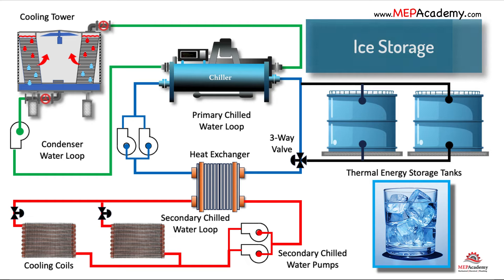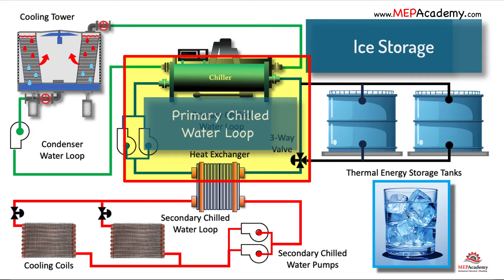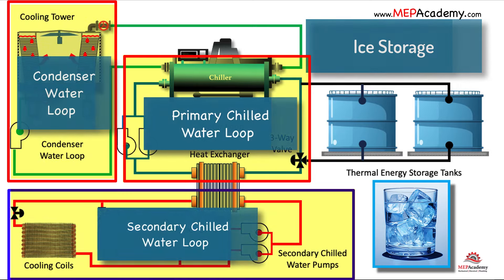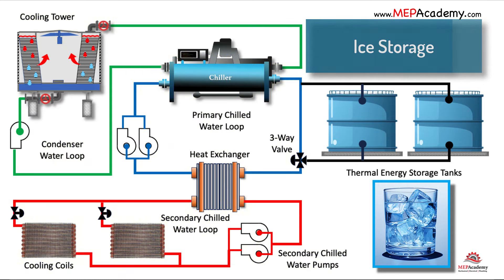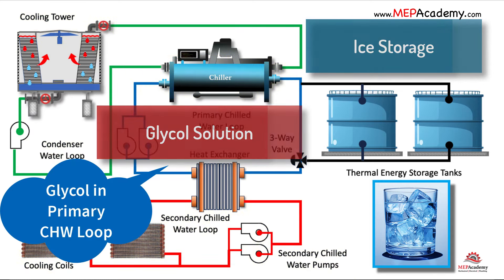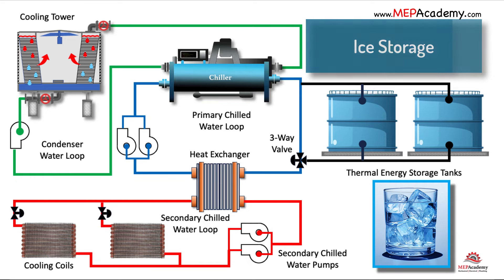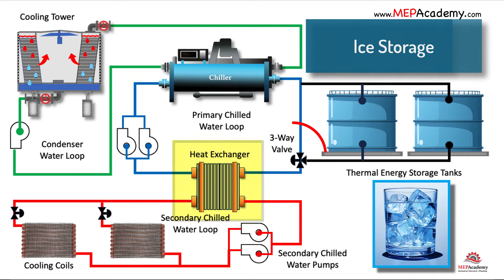In this image, we have the same water loops as the chilled water storage tank system: the primary chilled water loop, condenser water loop, and secondary chilled water loop. The difference with this system is that a glycol solution will circulate through the system in order to produce ice on the coils within the tanks. Glycol prevents the water from freezing. A heat exchanger will separate the primary and secondary loops, and the three-way valve and control sequence will control the flow of water to and from the tank.